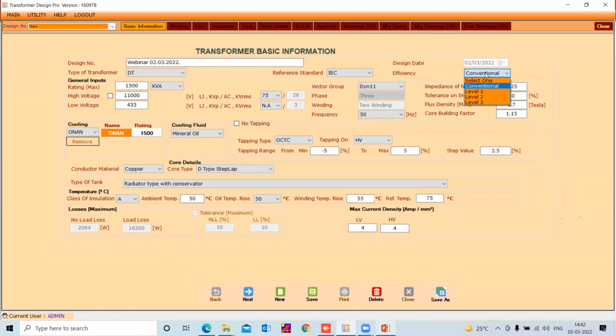You have 4 options over there. The conventional talks about the highest losses. Level 1 is lower than the conventional. Then you go for level 2. Level 3 is the lowest losses. Let's go to conventional first and see on the left hand side bottom. You are in a position to see the no load loss of 2064 watt and load loss of 16,200. Now, the moment you go to level 1, you will see the losses reduce. Let's go for level 1. Okay, let's go for level 2.